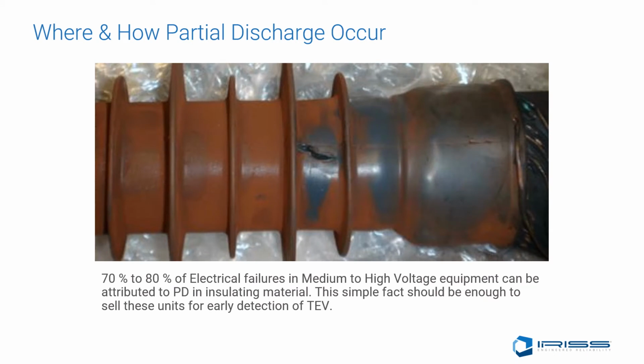So with 70 to 80% of electrical failures in medium and high voltage equipment being attributed to partial discharge in insulating materials, this simple fact should be enough to sell a company on the ROI of the Sonus PD product line's ability for early detection of TEV and ultrasonic emissions that would indicate fault conditions are present.